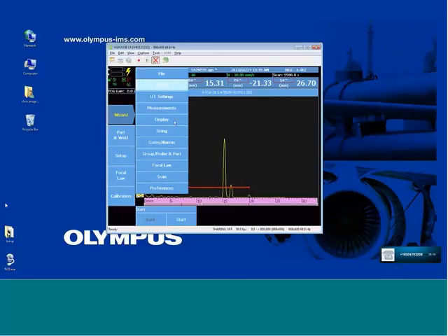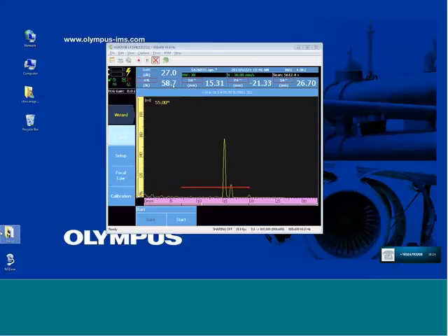We developed the wizards so that it was not necessary to have to move to many different menu items to populate parameters for a basic setup. So selection of the menu wizard enables the part and weld, the setup, focal law, and the calibration.